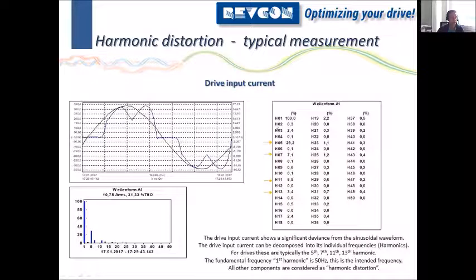So you would have measurements, and these will give you some information. The first one would be the current shape. This is a power quality analyzer in this case. It will give you information about the current waveform. It will give you all the individual harmonic values, in this example as a percentage, which could also be a current or a voltage. It will give you individual values of the individual harmonics, up to 50 on all power quality meters today, or maybe up to 25 on some cheaper brands. Then you will see this kind of diagram showing you where you have harmonics. The most typical ones are 5, 7, 11, 13. That's a typical distortion of a drive with an internal inductance, inside the drive or outside the drive, it doesn't matter.